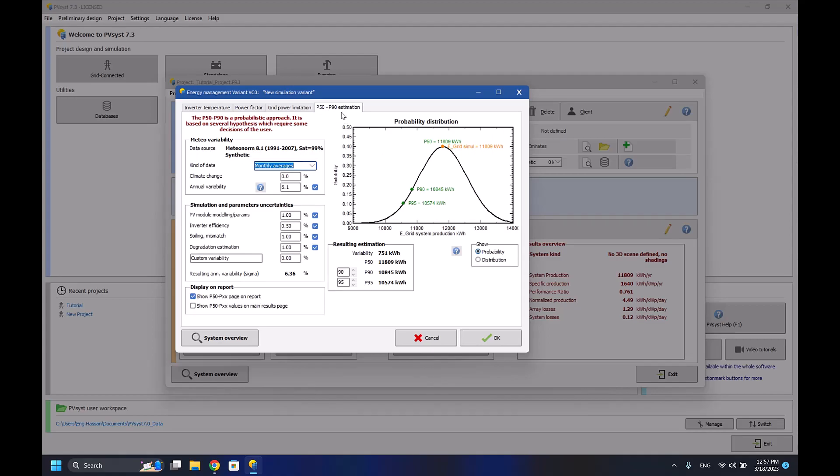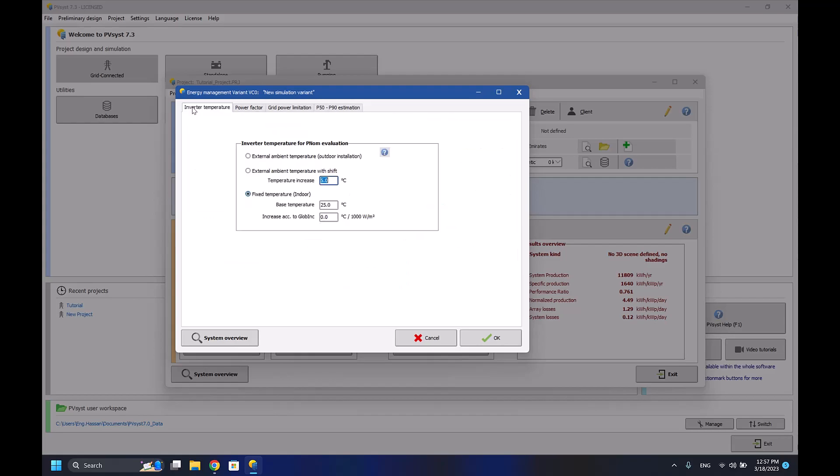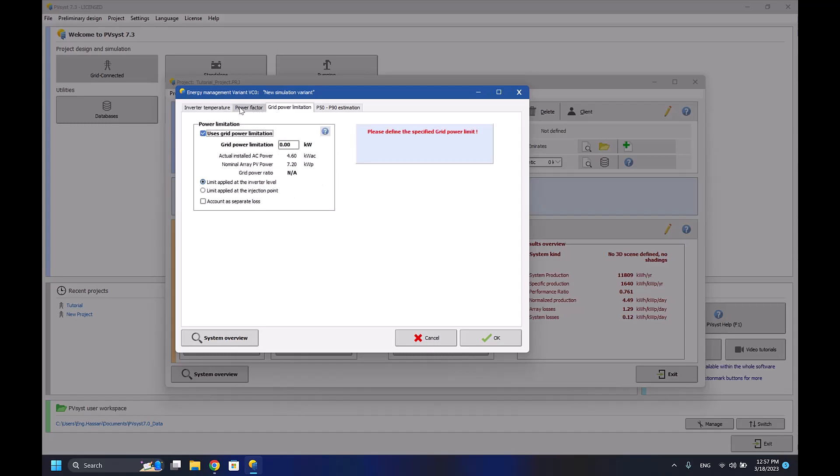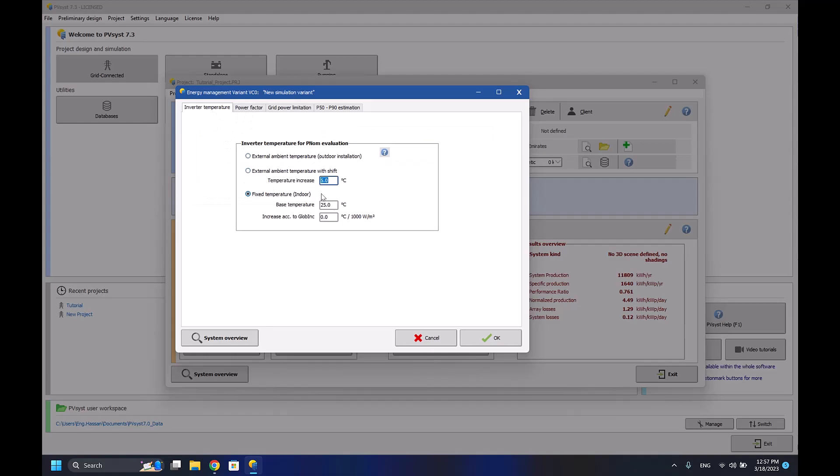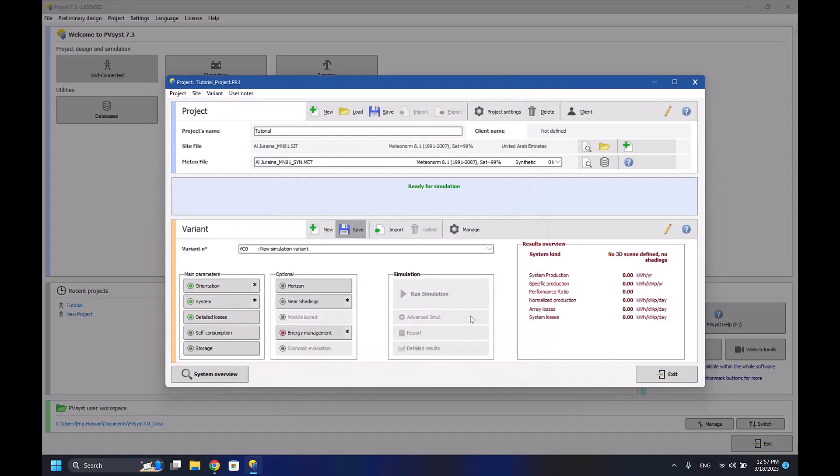I really don't have a lot of information about P50, P90 estimations because they are not really used in the real case scenarios. So engineers only take care of the inverter power factor and grid power limitations. Most of the time, there are no grid limitations for power selling, and inverter temperature - increase it by 5 degrees, 7.5 degrees depending on the type of inverter and the maximum operating temperature the inverter can work on.